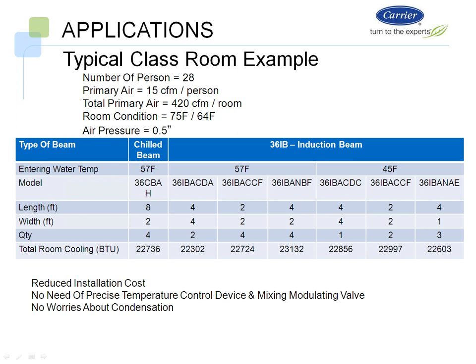where you think that might be the cheaper install. And that's always been one of the barriers, I would say, to chilled beam entry in the North American market, as well as typical install cost. And now when you're looking at this, we're finding it very comparable, if not better, than some of our standard systems. Again, remember, you're running smaller ductwork, less ductwork, fewer connections, and fewer pipe connections.